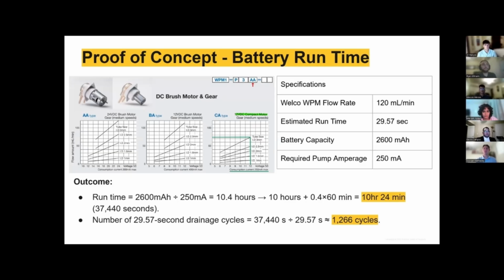And then, just going with that Welco WPM at 120 milliliters per minute, we calculated our runtime. Runtime is about 30 seconds. Inside of our housing, we'll be using a 2600 milliamp hour battery. At the required amperage of the pump, which is 250 milliamps maximum, it turns out that we can run the pump for 10.5 hours off that battery and just over 1,000 drainage cycles, which is pretty impressive for such a small battery and pump.